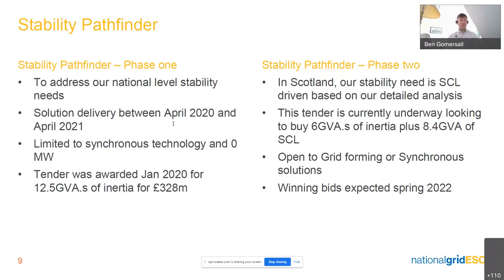We followed that up with a second one where we're looking at both the inertia and the regional short circuit level. That was going to focus on Scotland only, so we've identified a specific need in the Scotland area. In that one, we were looking to buy an additional 6 GVA seconds of inertia plus some short circuit level. And critically for this tender, we decided to open it up to grid forming technologies as well as synchronous solutions.